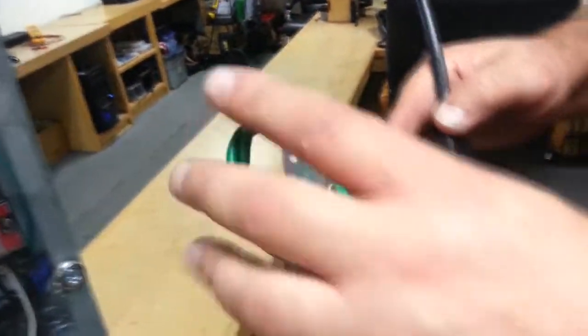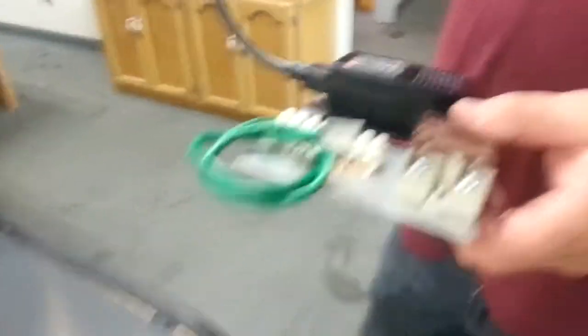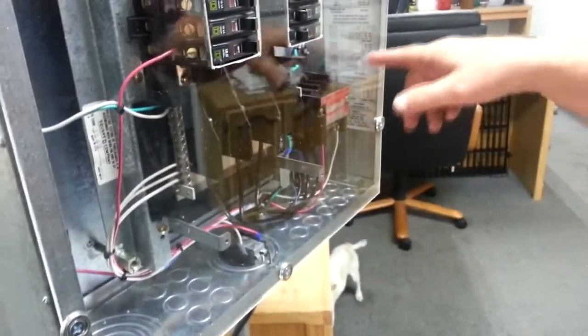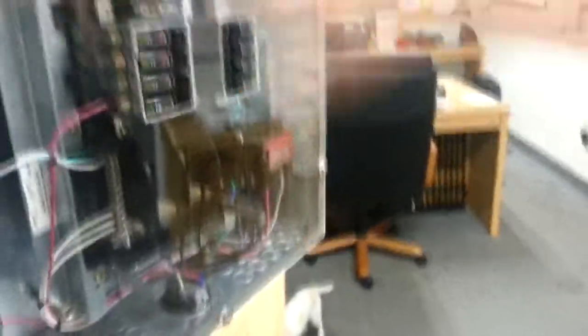Because in addition to turning on the lights, what you have is a relay that's built into what we call the panel assembly. So the main sensor controller consists of that sensor and this panel assembly and the panel assembly comes pre-wired with the cat six cable on it. And as you can see in the panel, there's your panel assemblies, the cat six plugs into that coupler, which picks up the outside connection. And then this is my solid state relay. So there's really nothing you have to do inside on the low voltage side of this thing. You have to get power to this, which is done here. And you have to open and close the coil that runs this relay. Very simple stuff. Very simple stuff. This relay runs all of these breakers. So this is a very typical application.